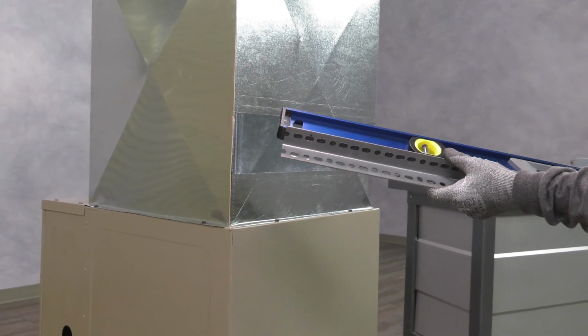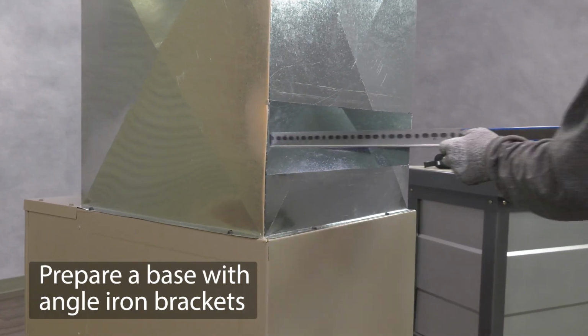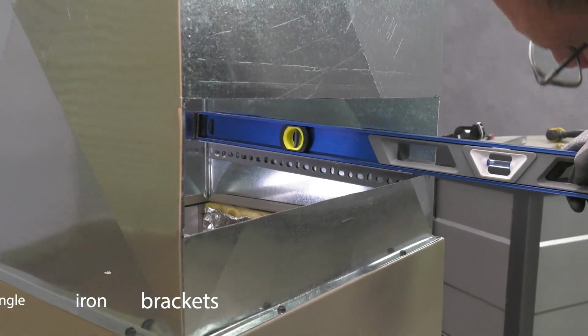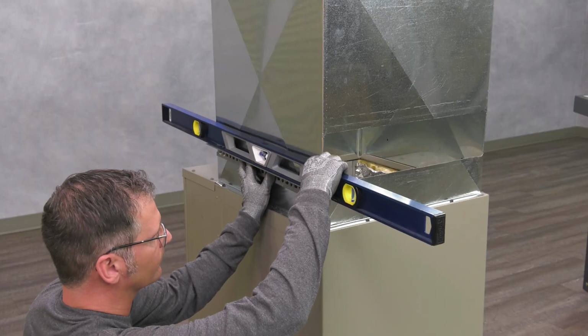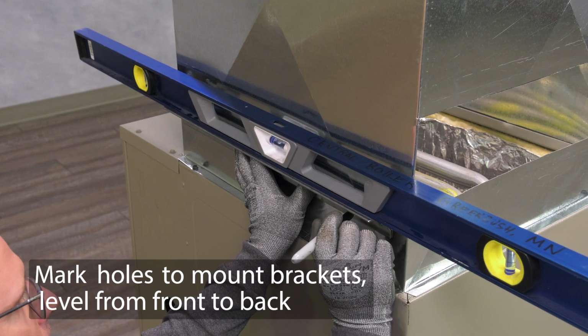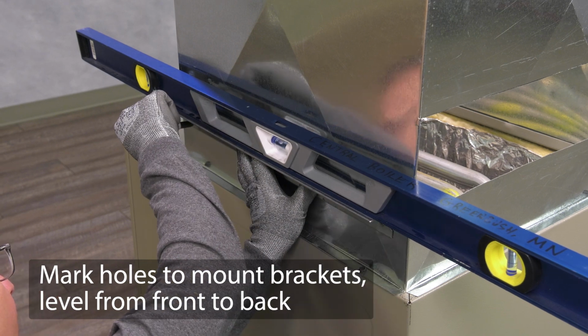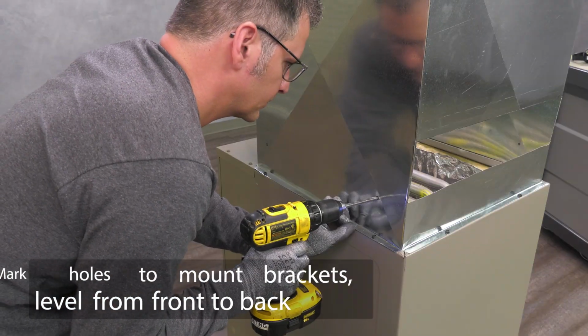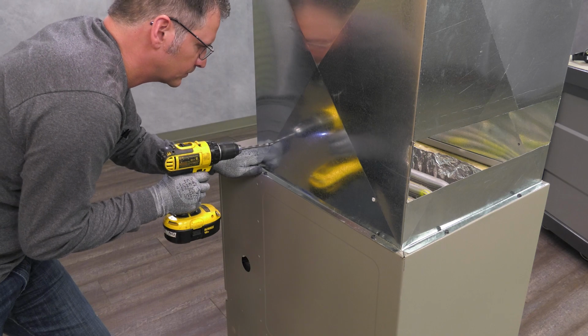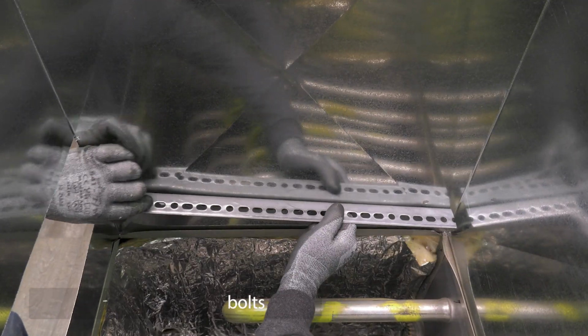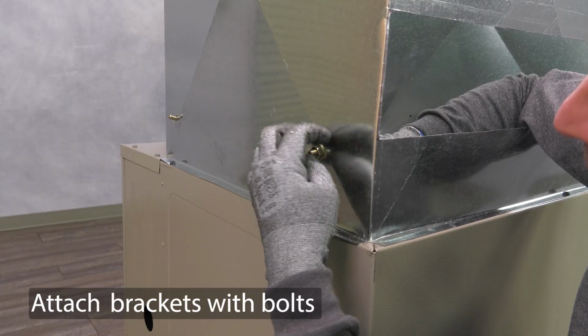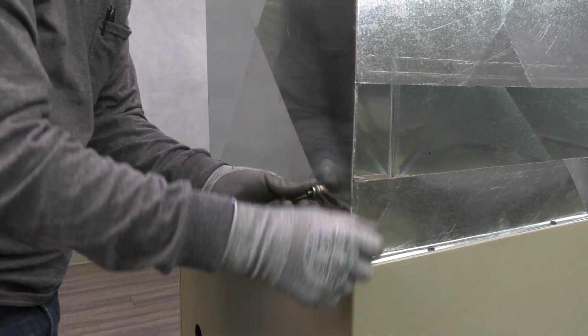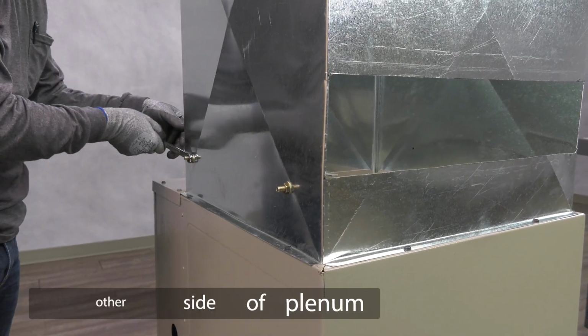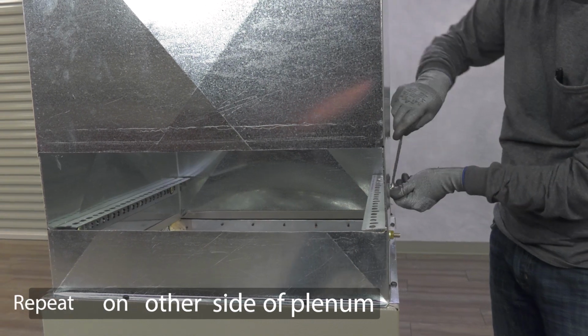Prepare a shelf or base with angle iron brackets to support the heat exchanger. First, measure and mark holes where the slotted angle bracket can be mounted, making sure they are level from front to back. Drill the holes in the plenum for mounting the brackets. Attach the brackets with the bolts, ensuring the brackets are level. Then tighten the bolts. Repeat this on the other side of the plenum.